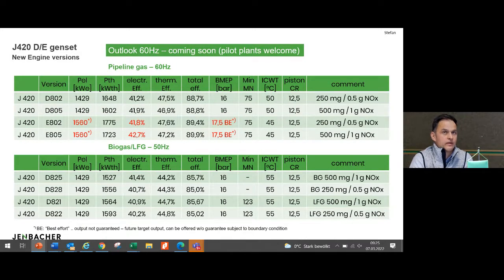What's coming next? We have finished the internal validation of the 60 Hz products. So we are looking now for some pilot plants. So feel free, if you have suitable customers, to let us know. Here we have now implemented as well the natural gas versions on 0.5 grams or 1 gram. And we are now implementing the steel piston versions with a higher power output, up to 17.5 bar currently, till the validation is now complete on a best effort basis. But this is our future target to increase here as well on the 60 Hz market, the power output, and with the corresponding efficiency increases up to 42.7%.